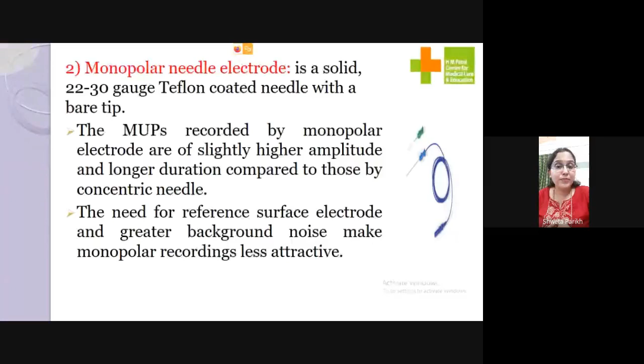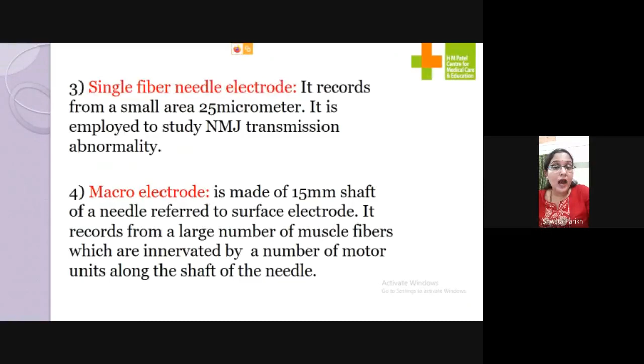Then the third type is the single fiber needle electrode. It records from a small area. The meaning itself, it's a single fiber. So it records from a small area, 25 micrometer. It is employed to study neuromuscular junction transmission abnormality. And the fourth type is the macro electrode. It is made up of a 15 mm shaft of a needle referred to the surface electrode. It records from a large number of muscle fibers which are innervated by a number of motor units along with the shaft of the needle.